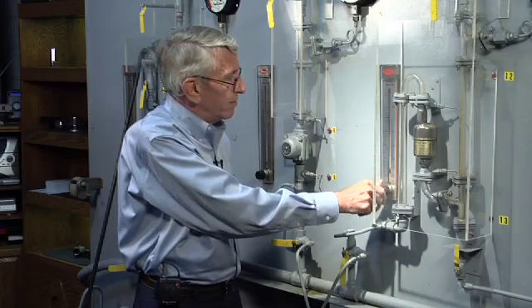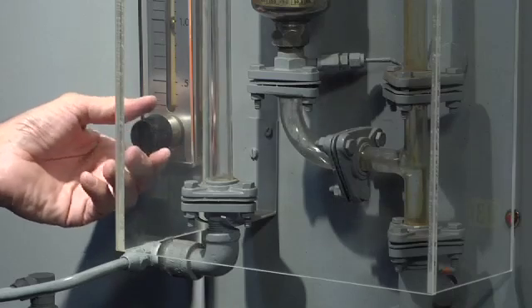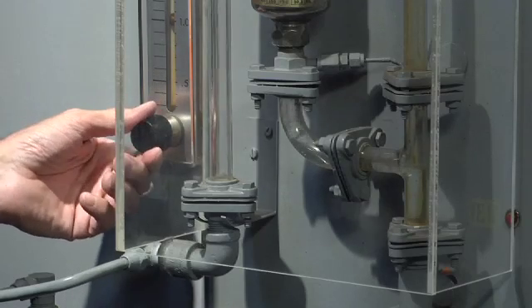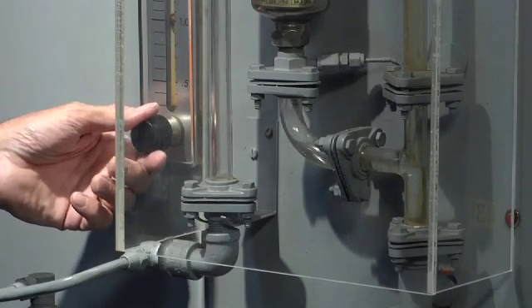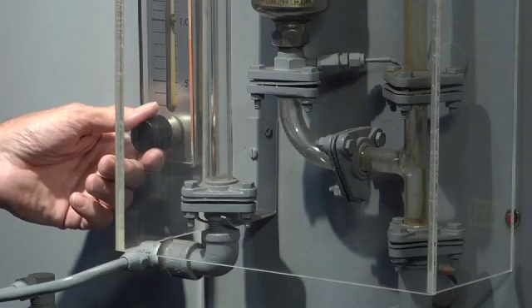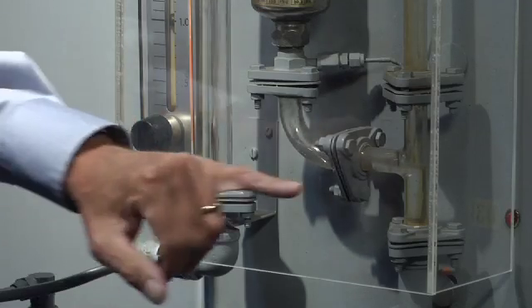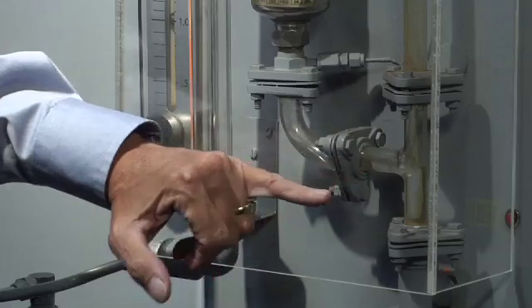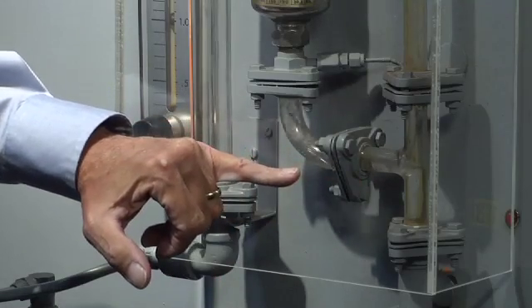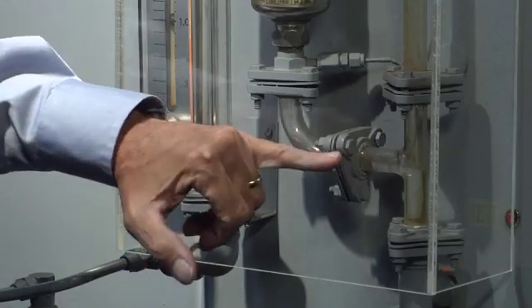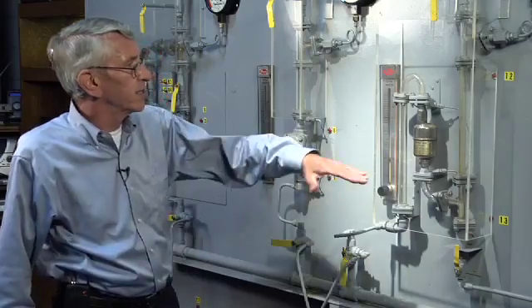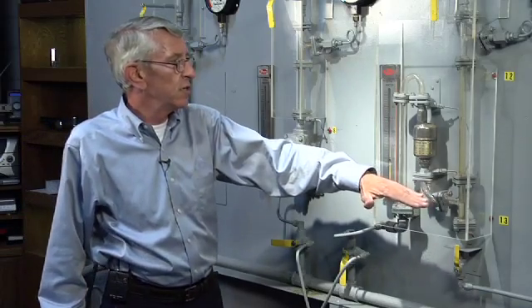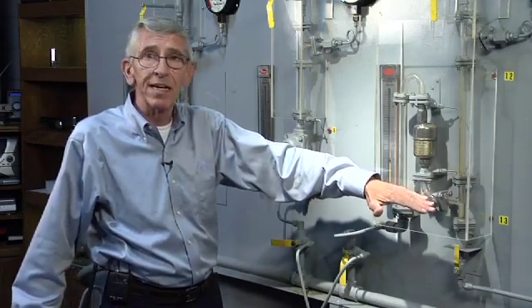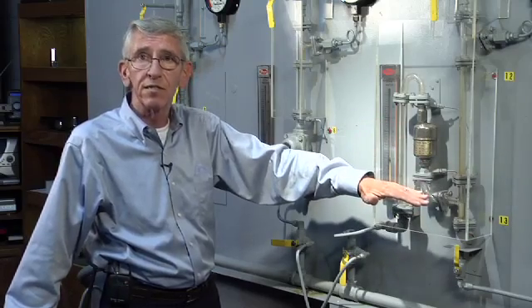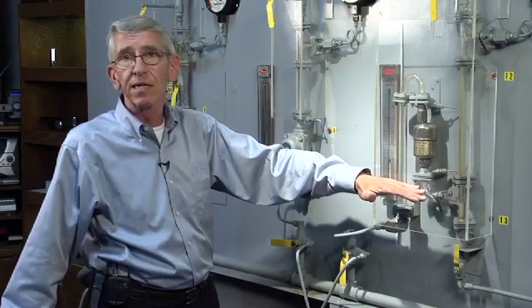I'll increase the load even further, going from 0.5 gallon per minute through the heat exchanger to 1 GPM, thereby increasing the load, and you'll notice that the condensate level does not change. As long as this trap is sized to handle the maximum amount of condensate that the heat exchanger can send to it, it is never going to back up condensate.